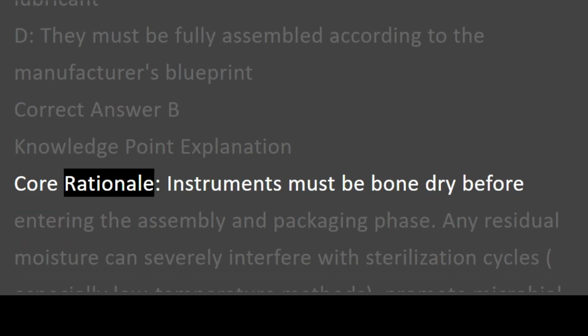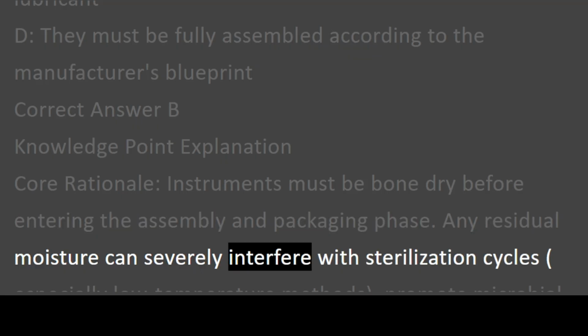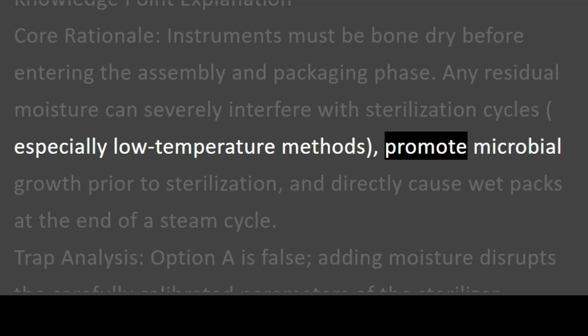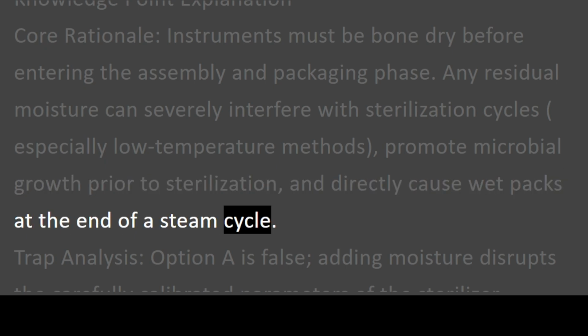Core rationale. Instruments must be bone dry before entering the assembly and packaging phase. Any residual moisture can severely interfere with sterilization cycles, especially low-temperature methods, promote microbial growth prior to sterilization, and directly cause wet packs at the end of a steam cycle.